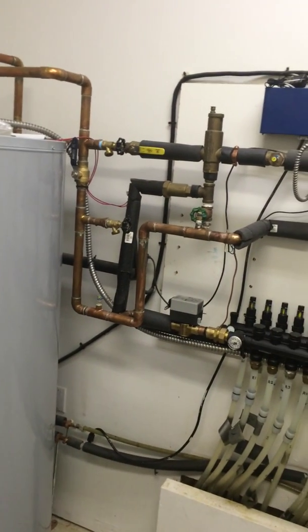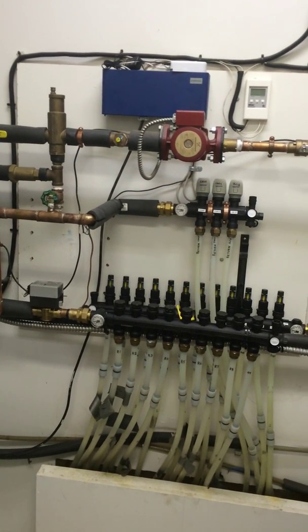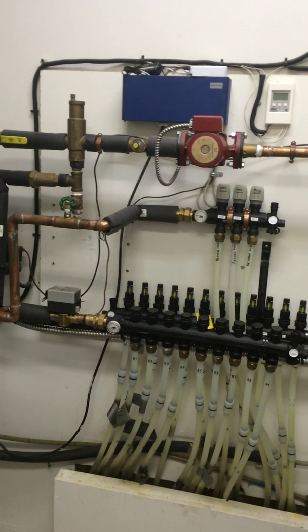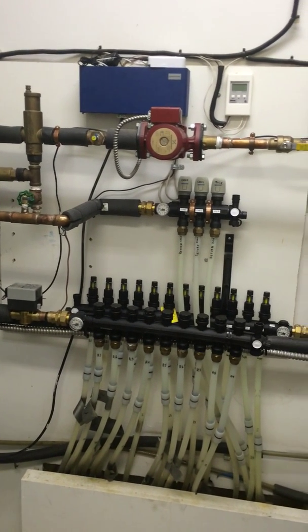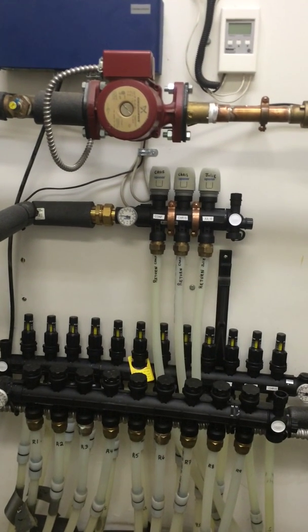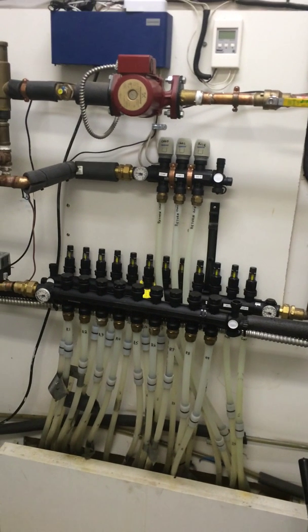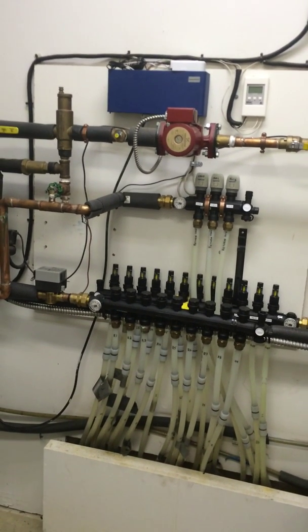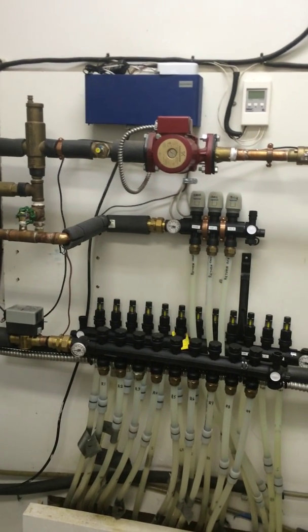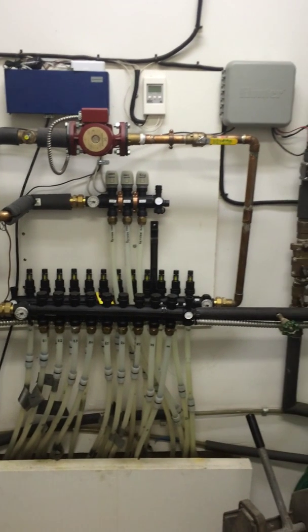This is a Water Furnace geothermal storage tank that's tied to this somewhat complex radiant floor heating system. Basically, you have a circulation pump that pumps the water to the floors with individual zone valves. It has a tekmar outdoor reset controller that keeps track of the temperatures outside so that it knows when to boost the temperature of the tank.